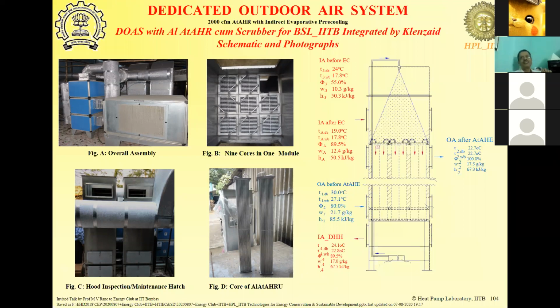Yeah, you see, on a 48 degree day, your unit will still do cooling. But it may not meet 100% of your load. So if you have designed it to maintain 27 degrees, anyway, on a 42 degree outdoor, you don't want to design with 27 indoor. You'll probably be happy with 32 degrees also.